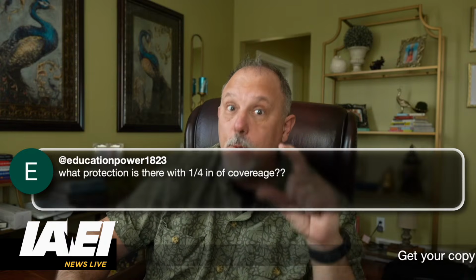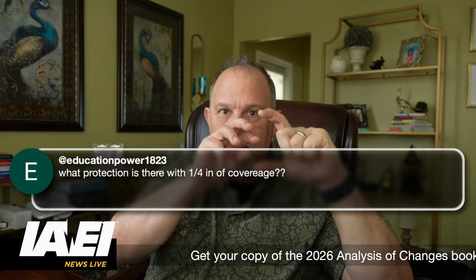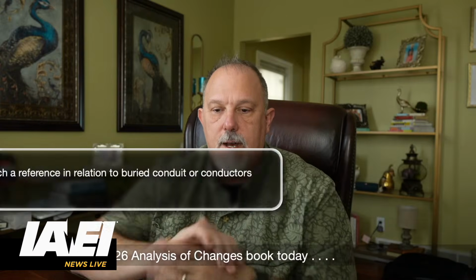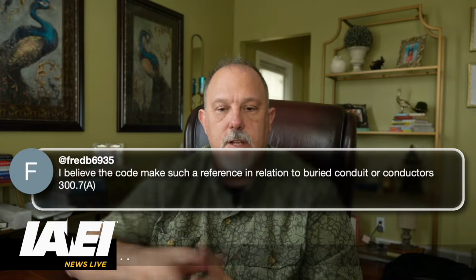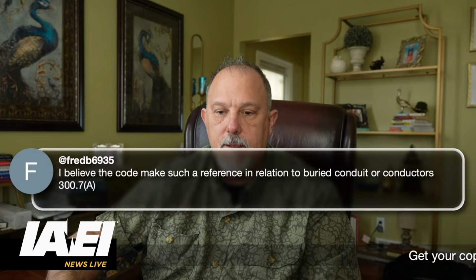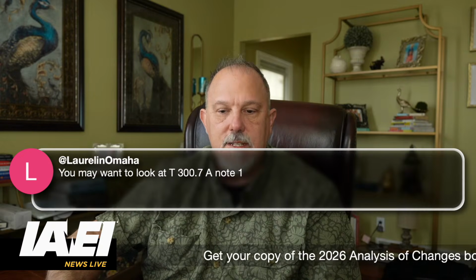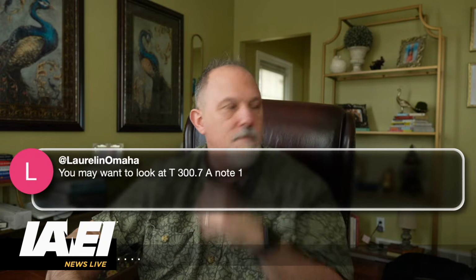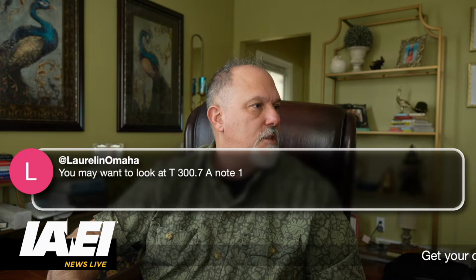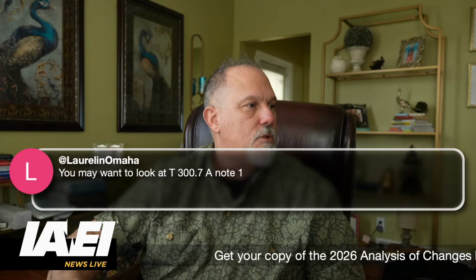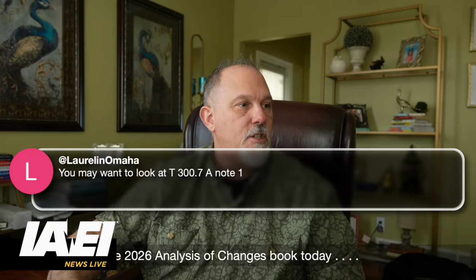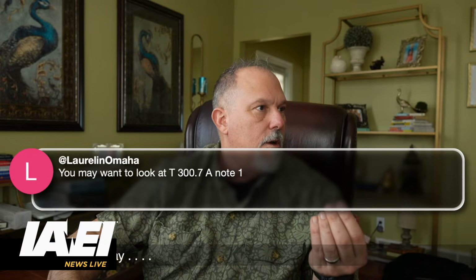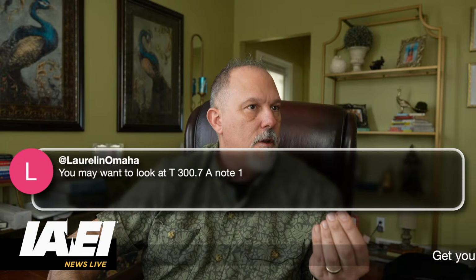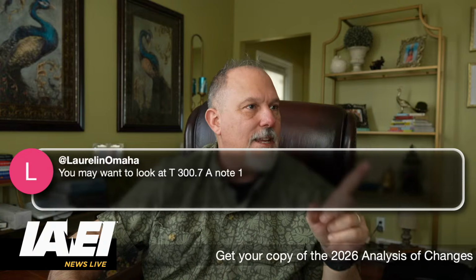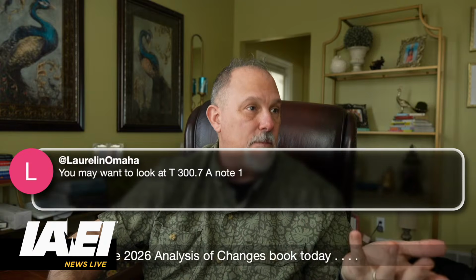But I could still say it's encased in 2 inches of concrete, because my 2 inches of concrete, my little raceway, I'm done. Freddie B says, I believe the code makes such a reference in relation to buried conduit. Yeah, buried conduit. You may want to look at table 300.7(a), 300.7, underground installation. Ooh, note 1, expand table. A lesser depth shall be permitted where specified in the installation. Cover shall be defined as the shortest distance in inches measured between the point on top of the surface. Yeah, but that's cover. That is cover. They don't use the word encased. Or they have encasement or other proof without concrete encasement.